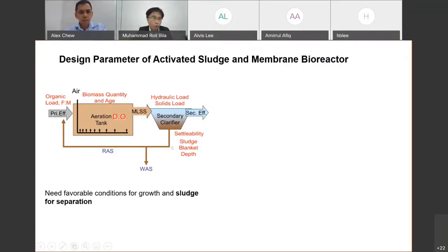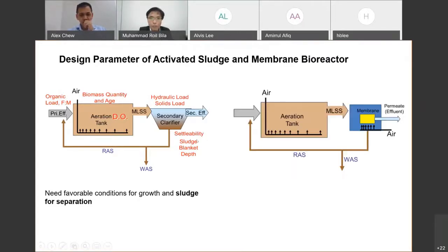In doing so, we need to adjust the loading, the concentration of the biomass, the dissolved oxygen, how much oxygen we provide to the system, and the hydraulic retention time, and then we also need to form sludge that settles easily. Okay, so these are the parameters that have to be optimized. As such, we will be able to achieve a good condition for growth and sludge separation.